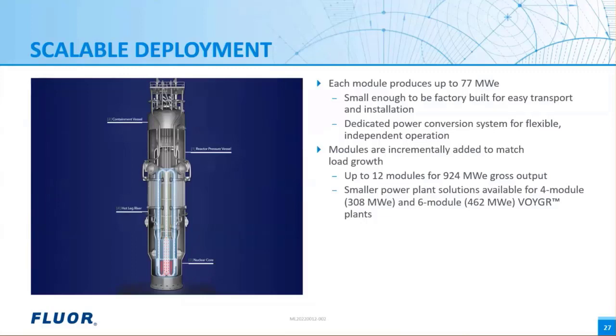The NuScale plant size is totally scalable. You can build one reactor building and then plug in the 77 megawatt electric modules as needed to support your load. Currently, up to 12 modules are envisioned for a 924 megawatt electric plant, which we have now coined the Voyager 12 plant. NuScale and Fluor are also developing smaller versions for various clients, specifically a Voyager 6 and a Voyager 4 version.